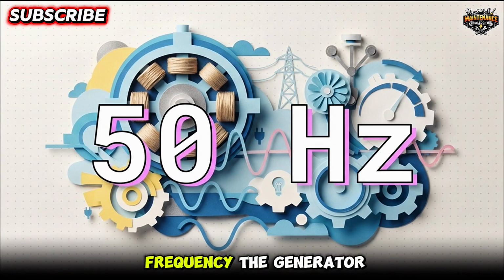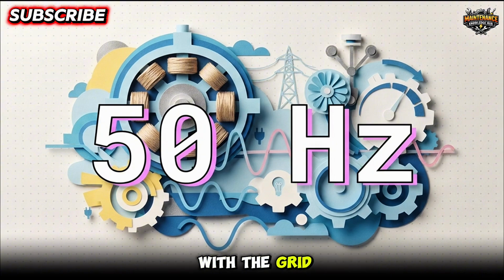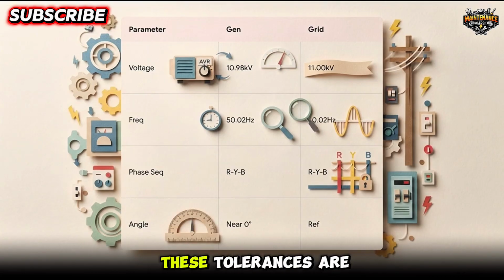Next up is frequency. The generator frequency has to be almost perfectly aligned with the grid frequency, which in a lot of the world is 50 Hz. So how do we actually control that? Well, we use the prime mover's governor, which dictates the speed of the turbine. To put that in perspective, for a typical 4-pole synchronous generator, hitting exactly 50 Hz means the governor has to hold the rotor speed at precisely 1500 RPM. Spot on.